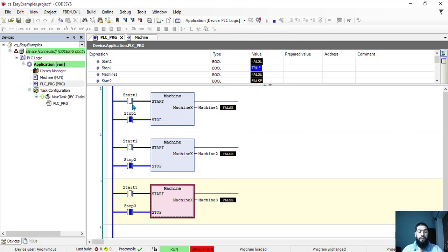We see each are different, but there is no conflict. Now our simulator is running, our stop button is normally closed, and this is what NC means. If you still have any confusion, an NC button means it's the physical button where the voltage is already applied to the PLC input. That means that input is high. Normally open is where the input to that button is not connected. You have to press to get the signal into the PLC.